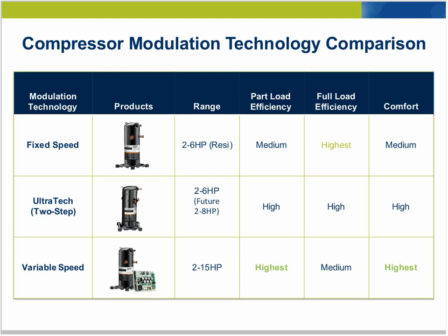Variable speed technology is the newest on the market, and it's typically a compressor coupled with a large motor control - you see it in that picture there. Some folks refer to them as inverter technology, and it has the highest part load efficiency. So when you're running it at low speeds, it's very efficient, but it only has medium full load efficiency. So on those really hot days, perhaps if you live in Arizona or whatnot, or the really cold days if you're in a heat pump, that's where it won't have the best efficiency. But it does have the highest comfort because it can match any load across a wide range.